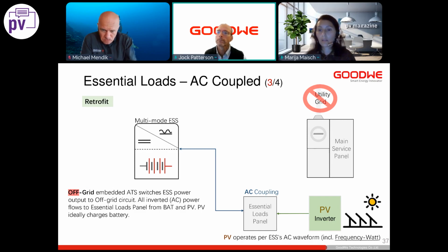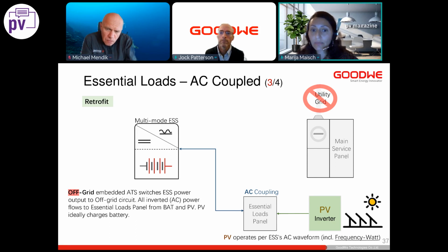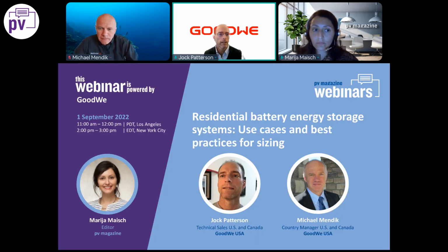Good question. Okay, you talked a lot about ATS. Someone asks, is this equivalent to the gateway on a Tesla Powerwall? An external box like a gateway is an external ATS — just a switching device. It may have other features like an auto transformer or metering, but the main feature is that it safely switches the loads over. That can be done inside the inverter, meaning you don't need an extra box, or in the case of the Powerwall, it's an external box, so you have to get an additional box to do that switching.